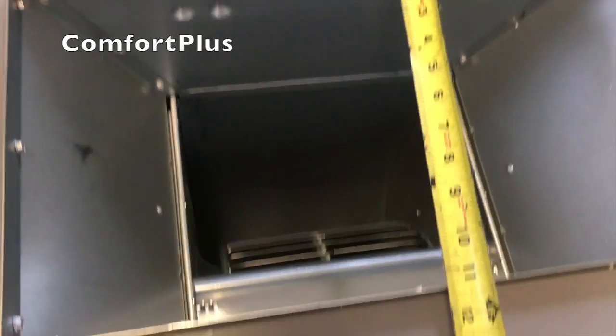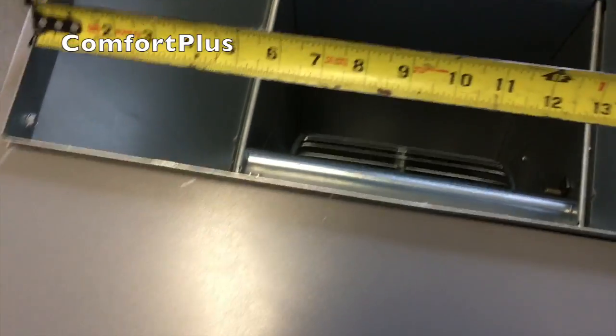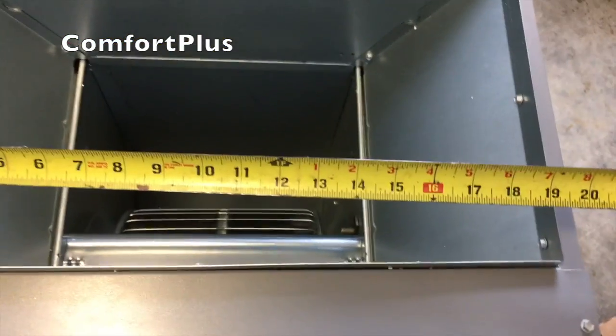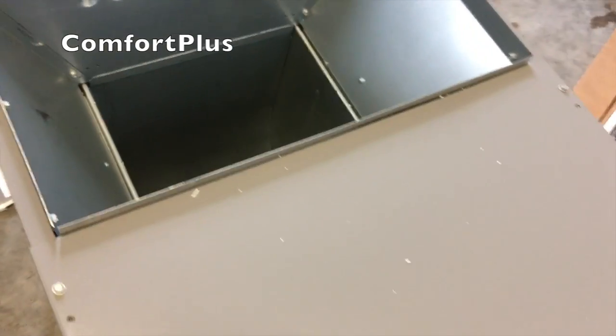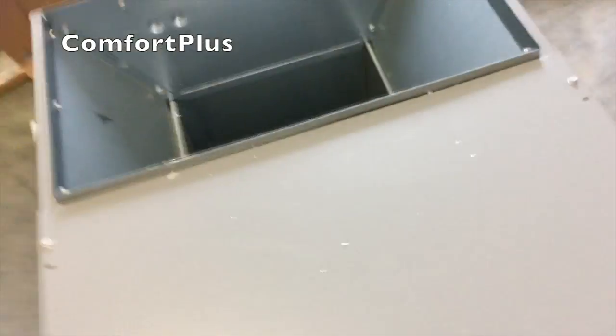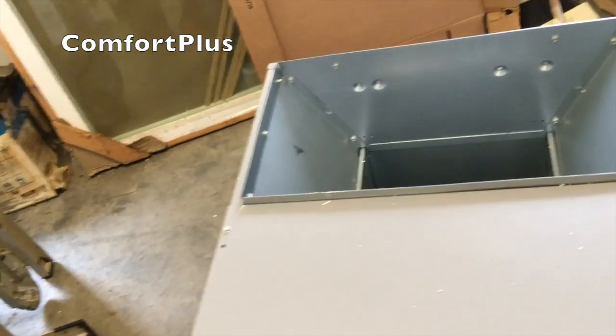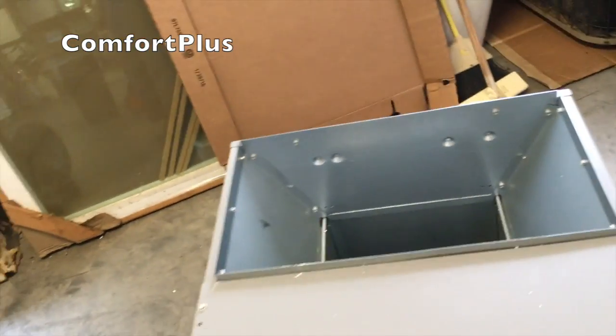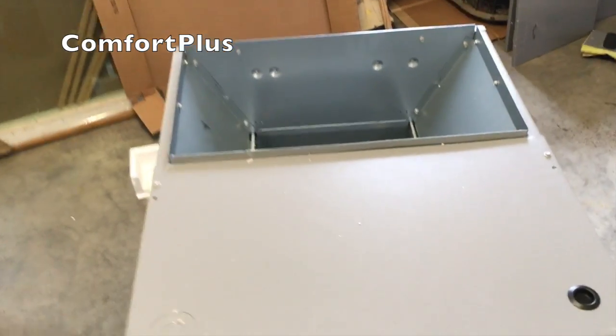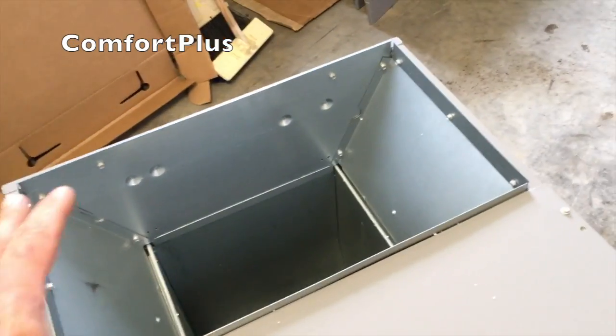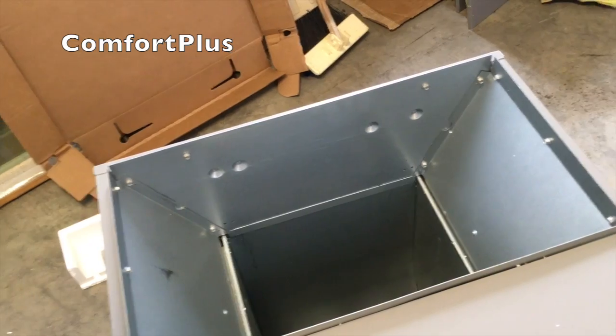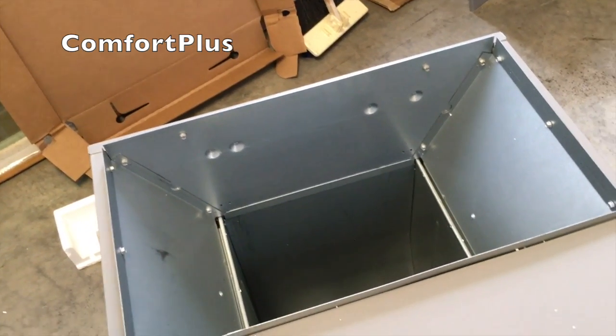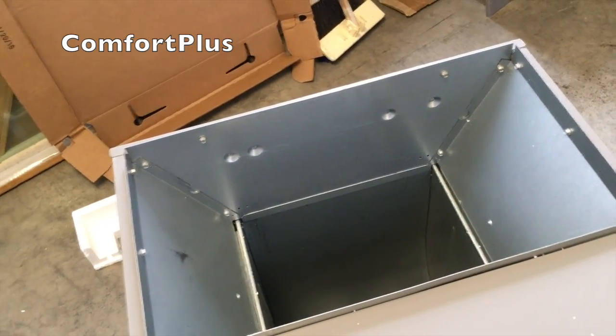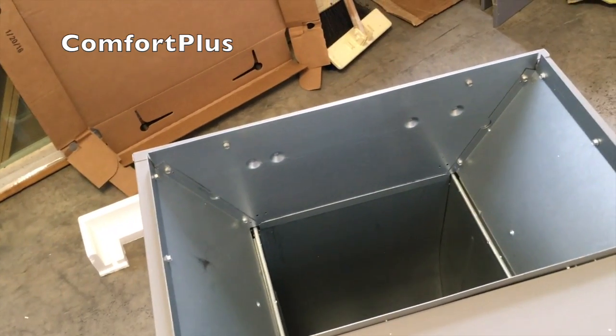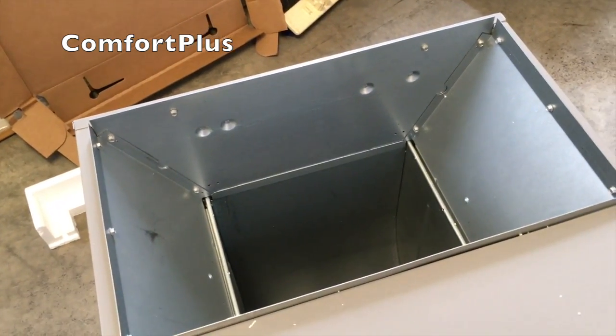is this discharge is 11 by 19 3/4. So what I've got to do, of course, it's going to be laying down flat. So it'll be 11 inches deep and right at 20 inches tall. What I'm going to do is make me a trunk duct that comes off this thing, a plenum, that I can go both directions to the 2 different zones that I'll be going to.